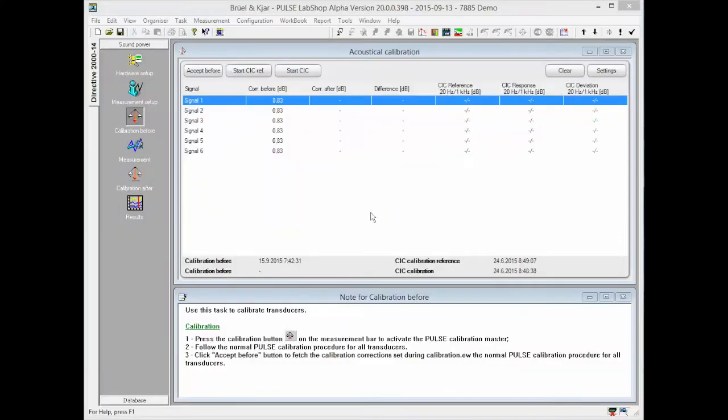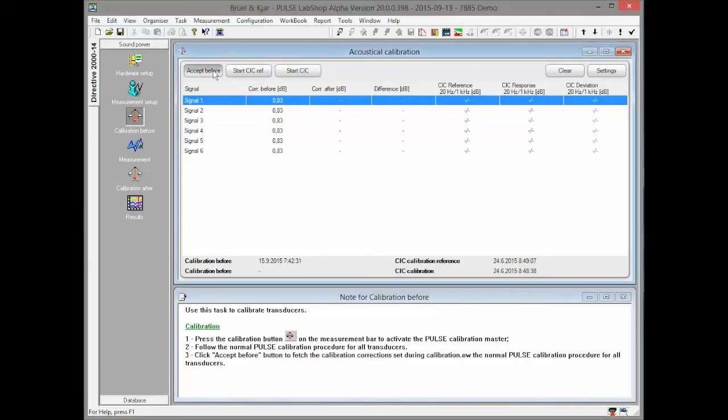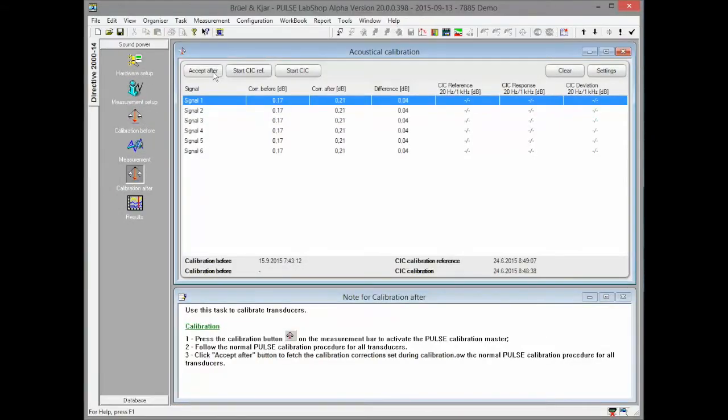If acoustical calibration is performed before and after measurement, 7885 offers a convenient way to store the calibration adjustments for every microphone input as required by the sound power standard. Once before and after corrections are available, the difference is displayed and indication is shown if the difference is out of permissible range.